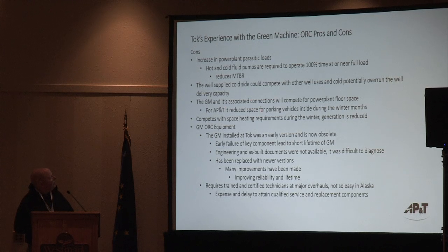Next thing here is space. The green machine is a very compact unit, but you can see the piping running into it. It ended up utilizing quite a bit of our floor space when it was in place. It wasn't too bad because it was nested up against the side of unit number 7. But when unit number 7 was taken out, we introduced a playground worth of things to jump up and over to get from one place to another in the shop. That should be looked at. We would probably consider, in fact, we are considering the next ORC installation to be an external installation where we pipe outside of the building, have all the ORC and condensing equipment outdoors.